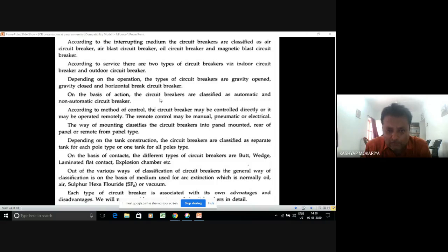I want to share one experience of my preventive maintenance. Once I was working on an ACB. We got the phenomenon that the 3 poles of the breaker were not closing or opening at the same time. Now this creates a big issue because my 415-volt breaker is connected to an LT motor. If this problem is kept as it is, then what will happen? Say R and Y will close, and after a millisecond or microsecond time lag, my B phase will close. So obviously it will cause single phasing to my machine, and if my protection relay is there, obviously it will trip the machine.